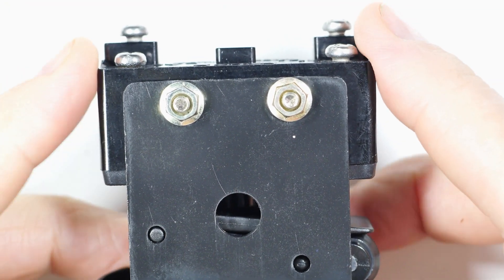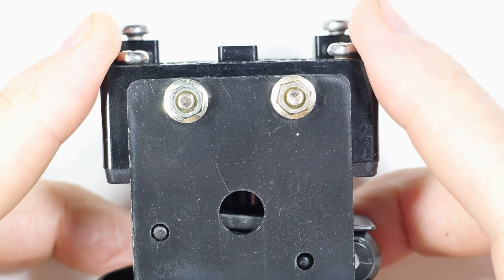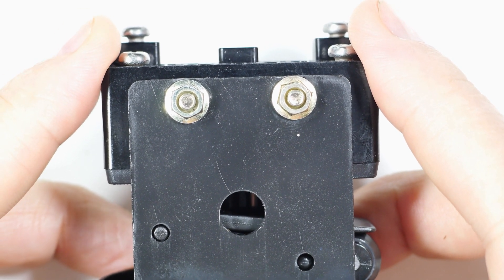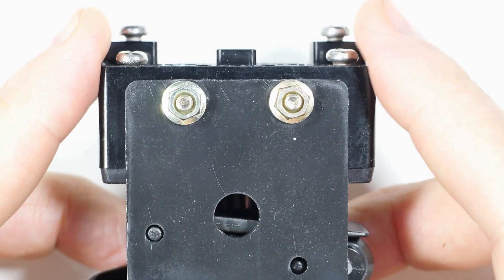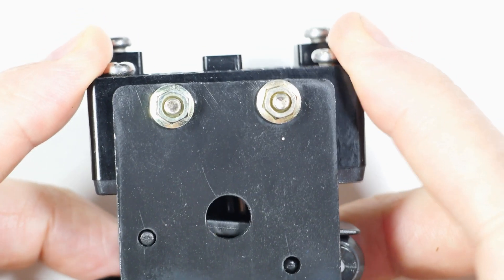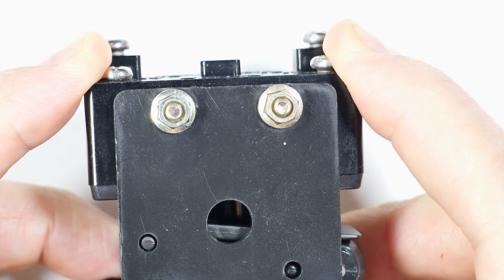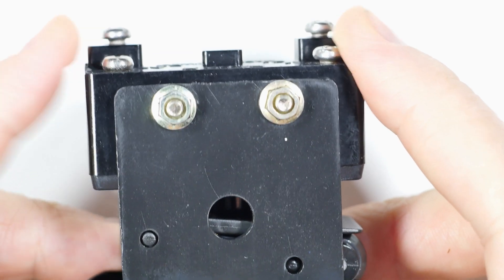When I got this particular switch it wasn't working correctly. I can't remember which one it was, normally open or normally closed, but it wasn't activating. What I found was, you see how much play there is in that? If I squeeze it all the way down and tighten the bolts, then it worked fine. So that was one issue.